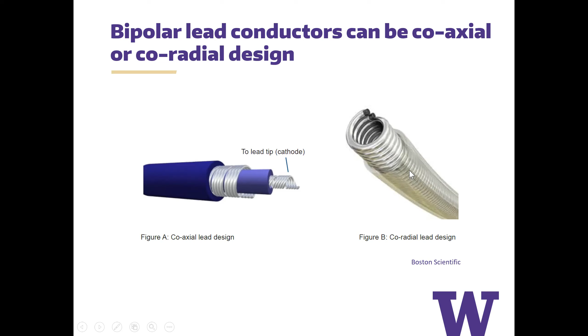So the basic pacing system uses a pulse generator plus the pacing leads. You need to have a pulse generator, and you need to have the wires. The implantable pulse generator houses the battery, and it houses the circuits. The circuits are typically an integrated microprocessor that controls the pacemaker. The pulse generator is enclosed in a very airtight titanium case, and the pacing lead is an insulated conductor wire that sends electrical signals from the generator and delivers pacing impulses to the heart.